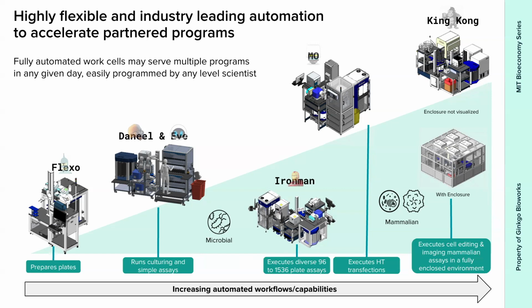But overall, building out integration where you center typically around a single robotic arm that is able to address different landing zones at commercially available laboratory hardware. So typically anywhere between like 15 to 30 pieces of hardware. You can think of liquid handlers, plate sealers, plate readers, in some cases even a flow cytometer can go onto a work cell. What you really want to be thinking about from a process optimization perspective is where do I find benefit in automating? I don't want to integrate for the sake of it because these are rather expensive.